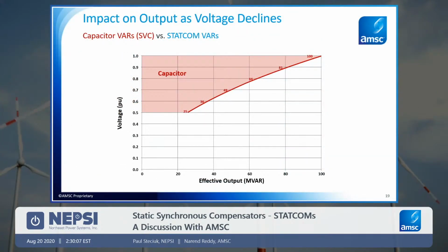And really, when you're thinking about cap banks, or SVCs, dynamic devices, you don't need them near nominal voltage. You need these devices for voltages that are changing way away from nominal. So you're expecting these devices to provide support at voltages that are 90% or less. But what you see is their output drops. This is where the studies need to come in to size: what's your deepest problem, the sag that you're trying to solve? That should dictate the size of the SVC. It doesn't necessarily have to be 100 megavar or 200 megavar. It'll be what is required to bring the voltages back.